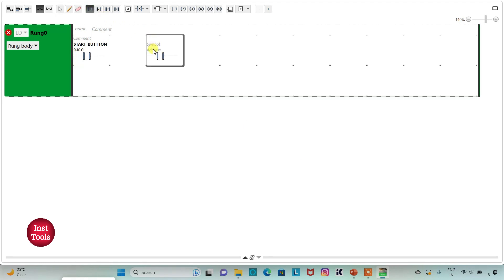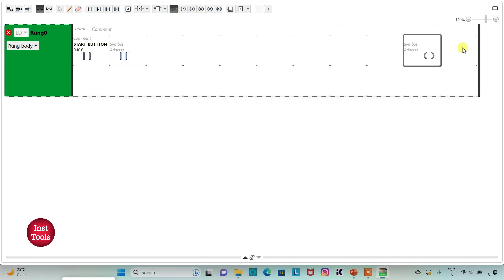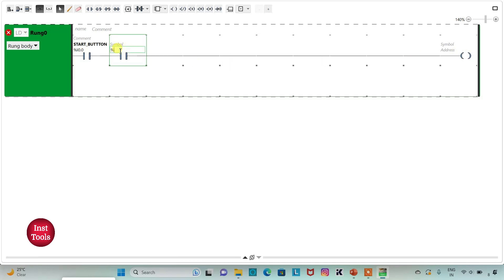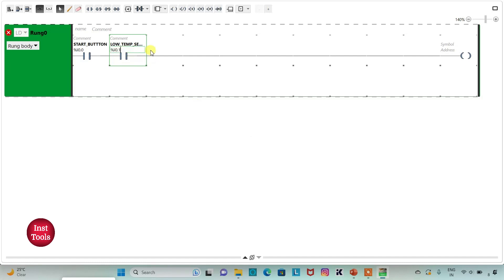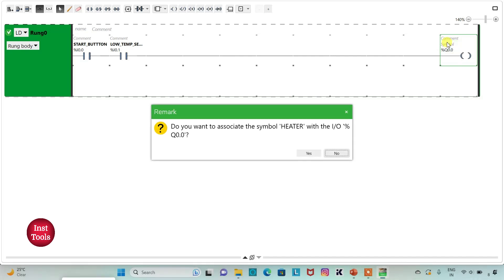Then I will insert one more normally open contact, and then insert a coil. I will assign the address I0.1 to the contact and add the symbol 'low temperature sensor' to it. I will assign address Q0.0 to the coil and add the symbol 'heater' to it.